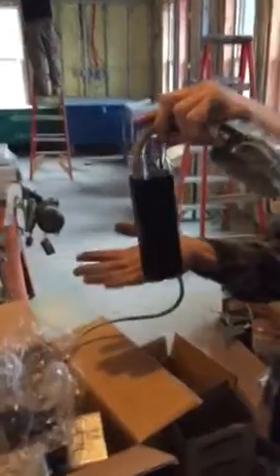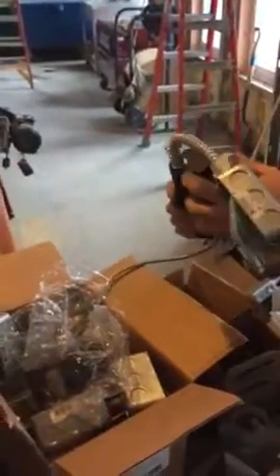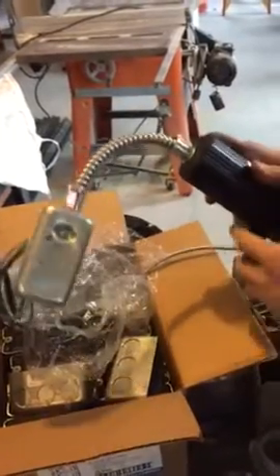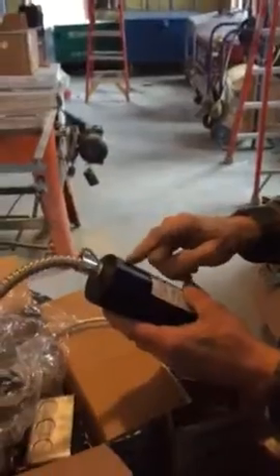Weren't you supposed to be able to wire straight to the driver? Yeah, but if you open this up, the wire nuts are completely straight up to the top. There's a plate that holds the driver all the way up to the middle. So to take an in-and-out flex like these, there's no room — no room to splice and terminate and shove them in there. There's no wiring compartment in this whatsoever.